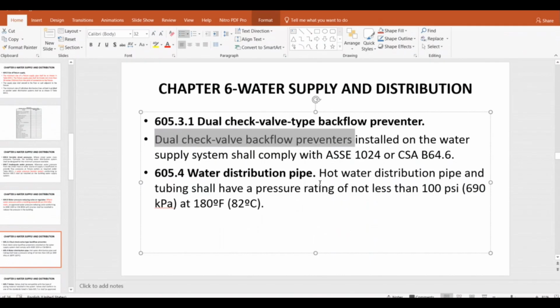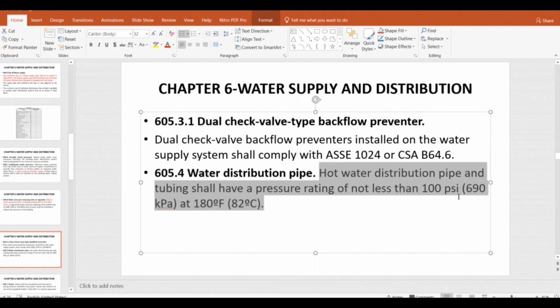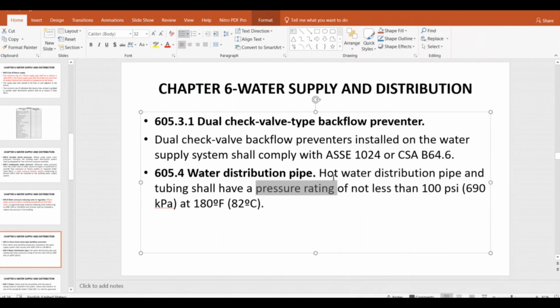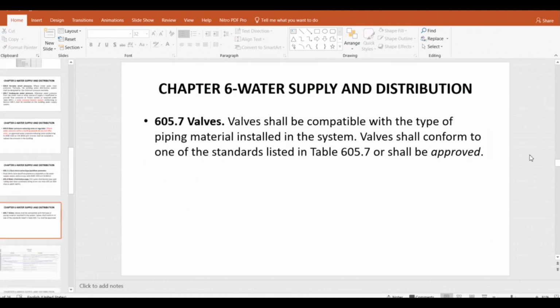Okay, so hot water distribution pipe and tubing shall have a pressure rating of not less than 100 psi. It means overall we have to make sure of the pressure rating for the hot water system pipe. For example, 100 psi is equal to 6.89, or 7 bar. So the pipe which we are using for the hot water system, we have to make sure that a minimum 7 bar pressure rating is provided for the hot water piping.